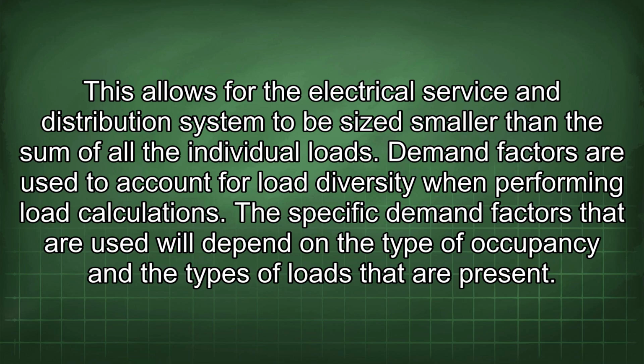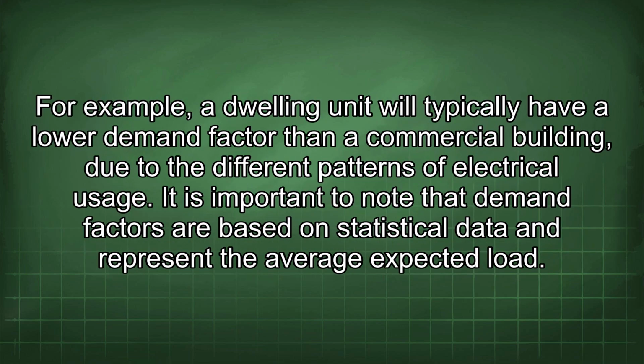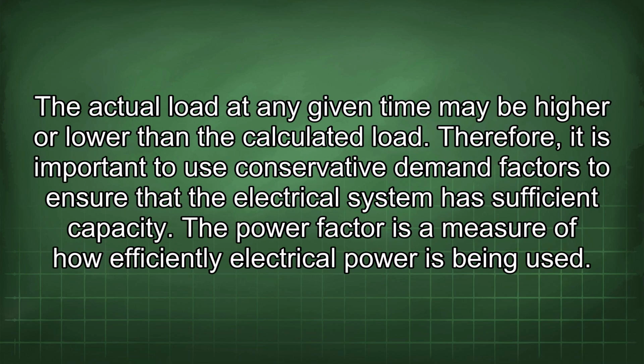The specific demand factors that are used will depend on the type of occupancy and the types of loads that are present. For example, a dwelling unit will typically have a lower demand factor than a commercial building due to the different patterns of electrical usage. It is important to note that demand factors are based on statistical data and represent the average expected load. The actual load at any given time may be higher or lower than the calculated load. Therefore, it is important to use conservative demand factors to ensure that the electrical system has sufficient capacity.